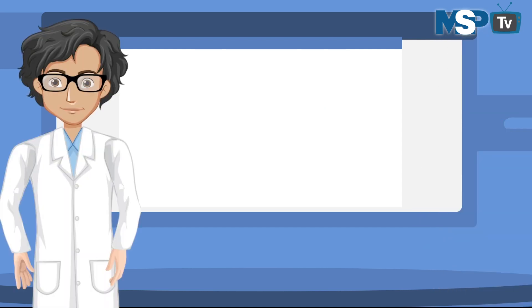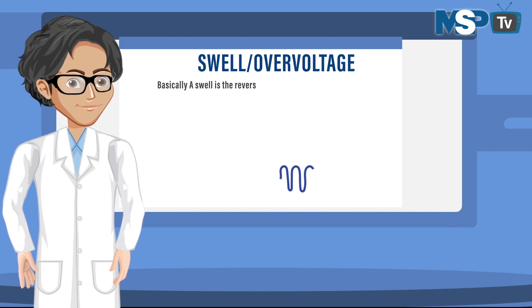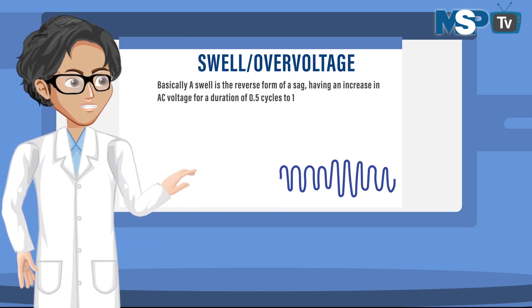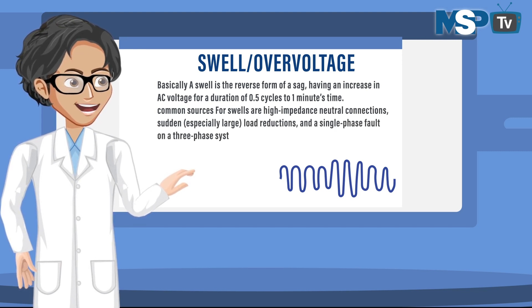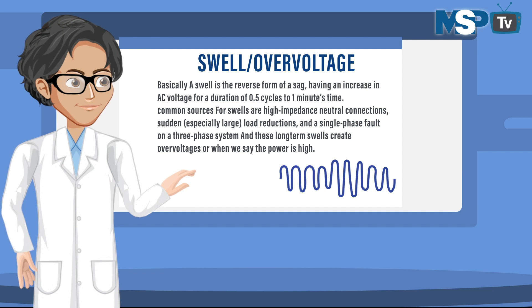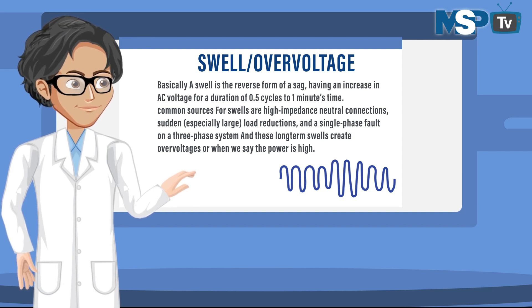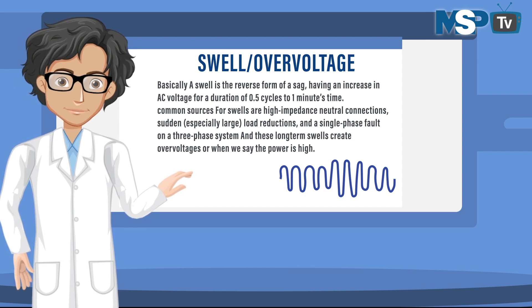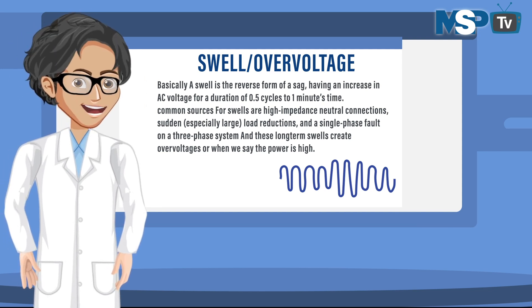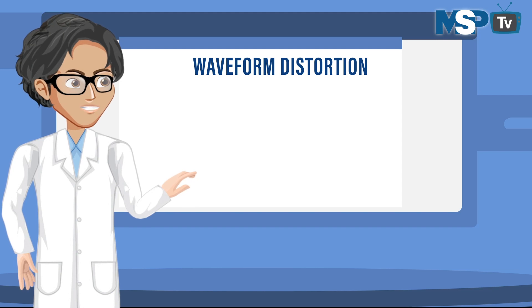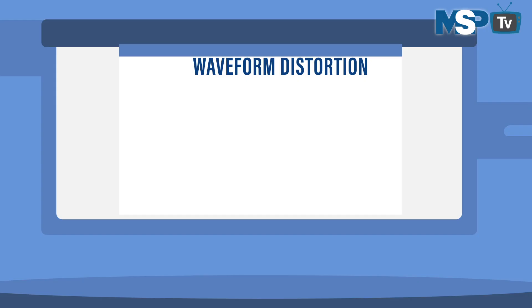The fourth problem is swell or over voltage. A swell is essentially the reverse of a sag — an increase in AC voltage for a duration of 0.5 cycles to one minute. Common sources for swells are high-impedance neutral connections, sudden or large load reductions, and a single-phase fault on a three-phase system. These long-term swells create over voltages, or what we say when the power is high.